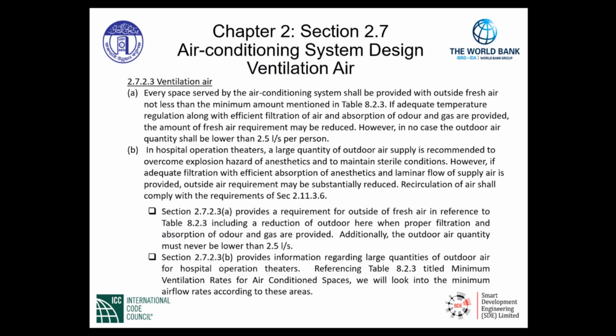regarding hospital operation theaters. Granted, we have a huge amount of outdoor air that needs to be supplied to overcome the anesthetics and maintain sterile conditions. In other words, you will see when we enter Table 8.2.3 the amount of air that is required for hospital operation theaters. The very last sentence gives the directive of recirculation air that needs to comply with section 2.11.3.6 if considered.